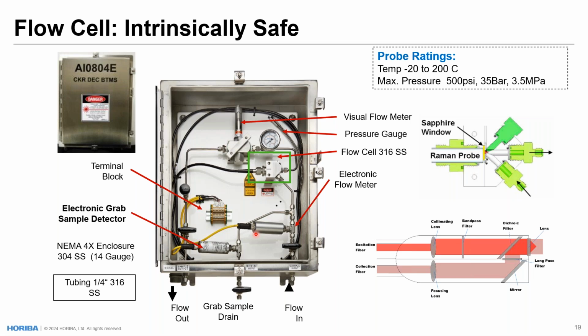Here is a little bit more information on the flow cell. Our customizable flow cell is intrinsically safe. It features a NEMA 4X stainless steel enclosure here and can continuously operate under pressures up to 35 bar, 500 PSI, in temps of -20 to 200 degrees Celsius. And NEMA here is a United States-based organization that sets standards for enclosure equipment like this in industrial settings.